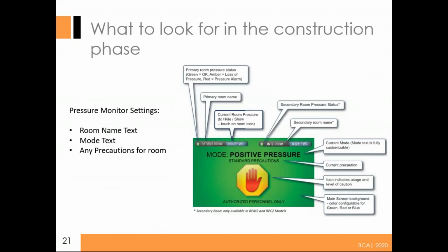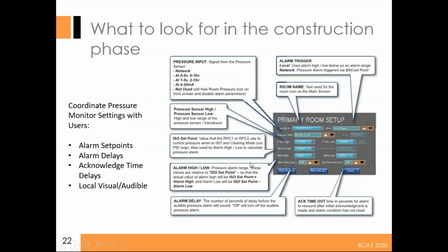Here's just a picture of a CRC. This happens to be the example here of a pressure monitor, showing some of the various things that you can edit. We typically set these up ourselves, so we work with the owner to determine how they want to set them up. You've got the room name and a secondary room name. The colors are adjustable, as is what you call these positive and negative pressures and these precautions. Precautions are more for isolation rooms and healthcare. But work with the users on how they want them set up. Again, I think the important takeaway here would be alarm set points.